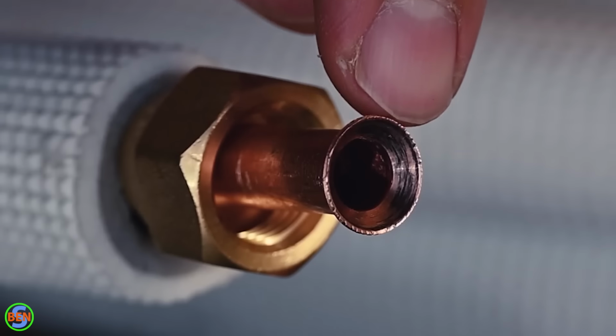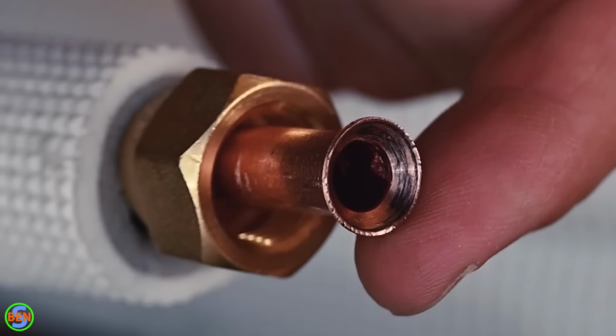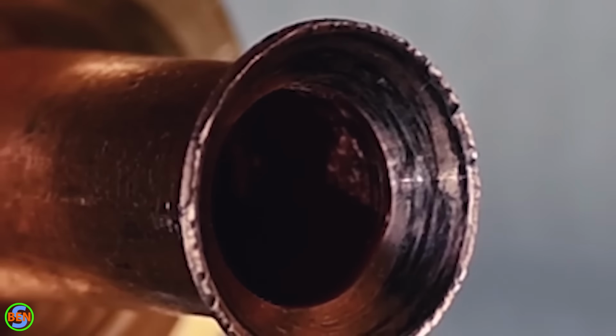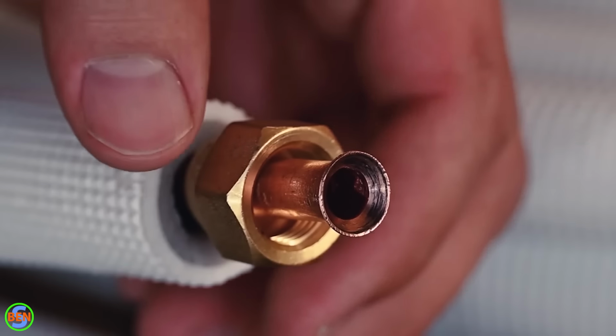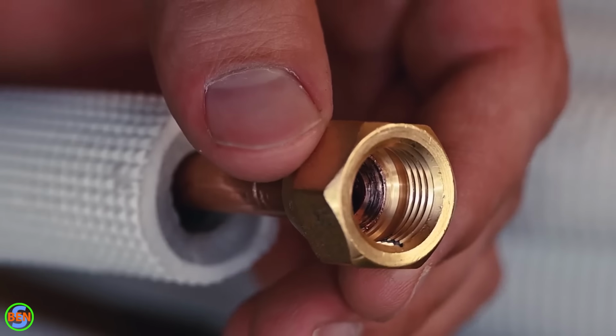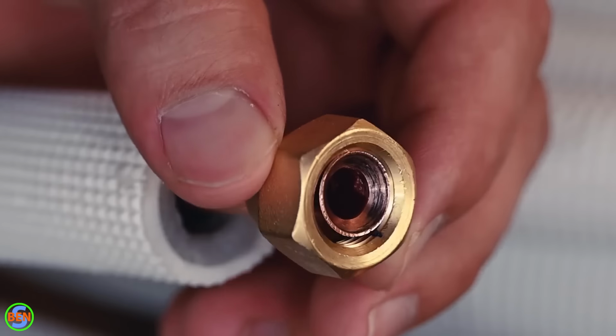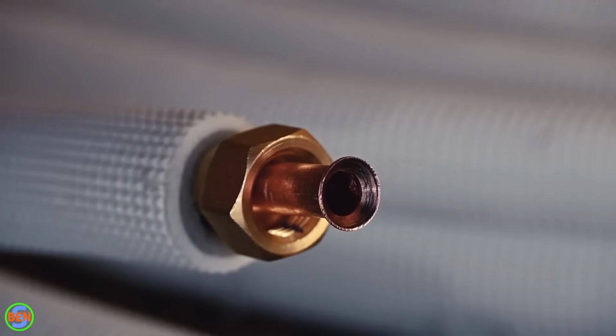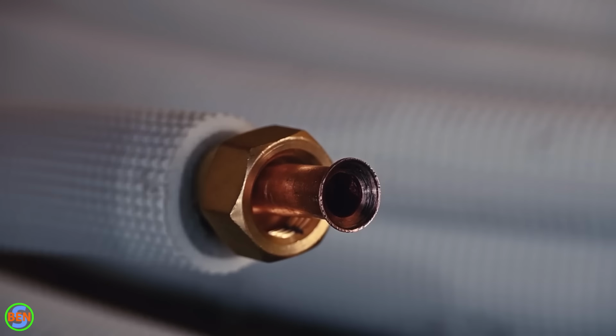You can see on the very outer edge of the flare, the copper is cracking a tiny bit, and that's not really a concern at all. As long as your flare nut goes over the top and rests properly, it's going to be perfectly fine. So this one's good to go. Let's go ahead and do our second flare fitting.